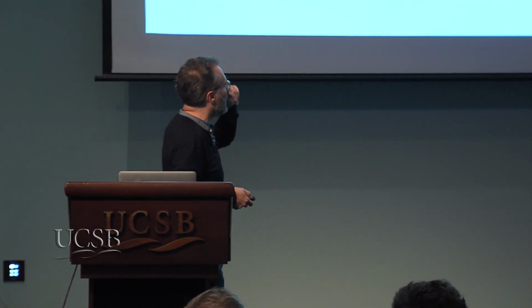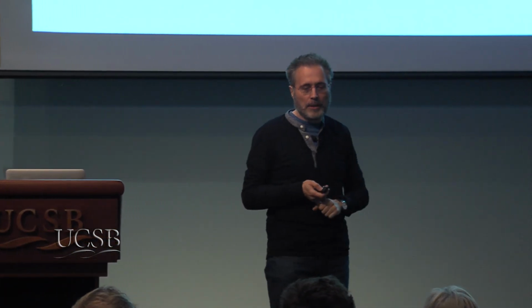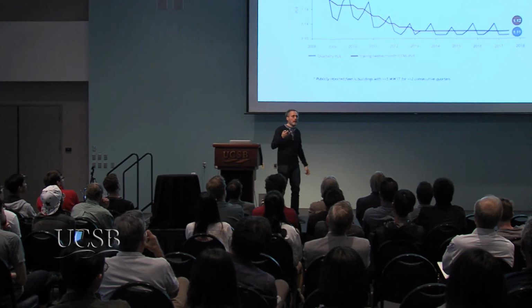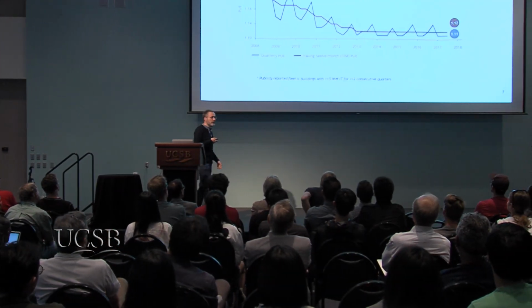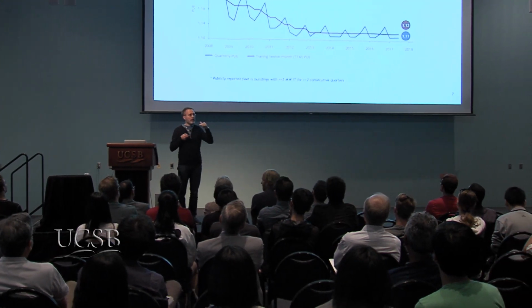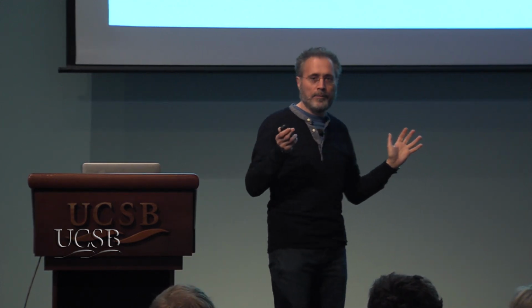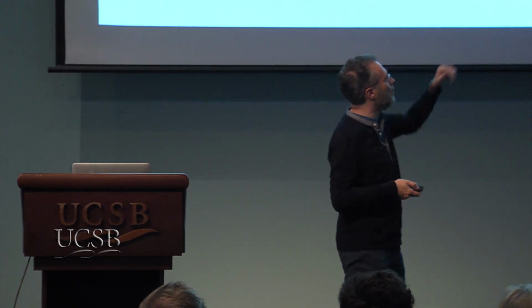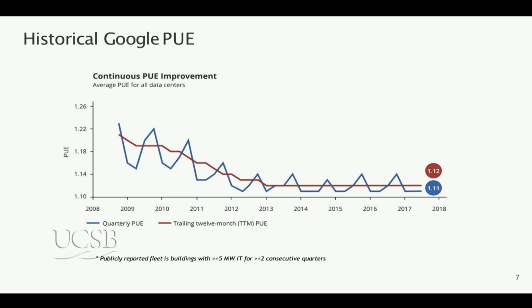This is actually what Google does - our average across all global data centers, including places like Singapore, Taiwan, and South Carolina that get pretty hot in summer, so it's not just nice climates. This is measured with PUE, power usage effectiveness, the ratio between total power consumed and actual IT load. 1 is the best possible value, meaning zero overhead. We're running at about 1.11 to 1.12 as a yearly average, so just 12% overhead. That's one reason this curve has come down - introducing a server into a Google data center only adds 12% overhead, mostly for cooling.